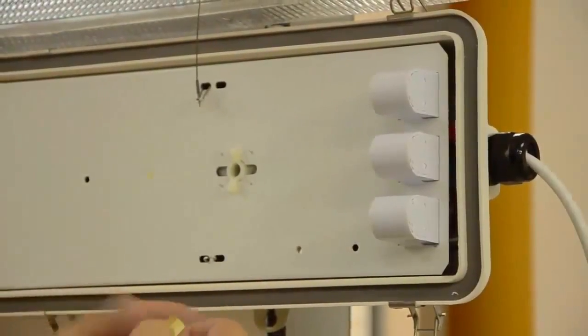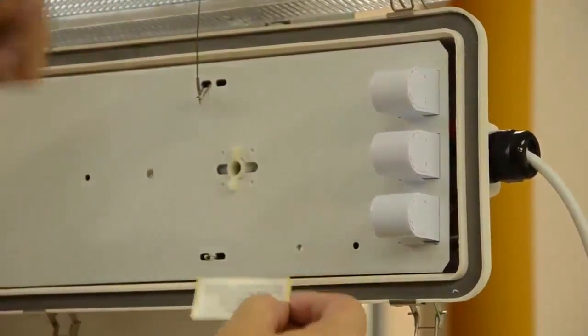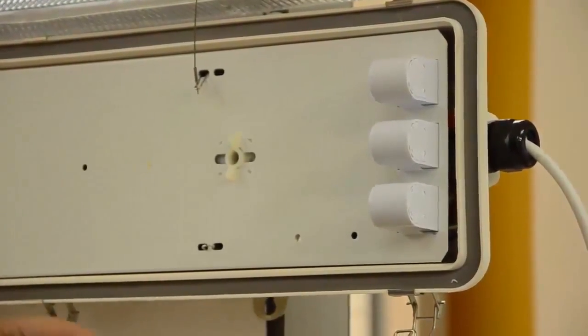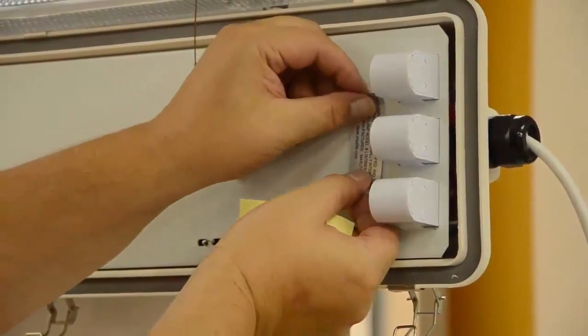Now before we put in our LED T8 lamps, I'm going to apply this label. This label is going to warn the next guy down the road 15, 20 years from now that when he does maintenance on this fixture that there is direct line voltage on these sockets.